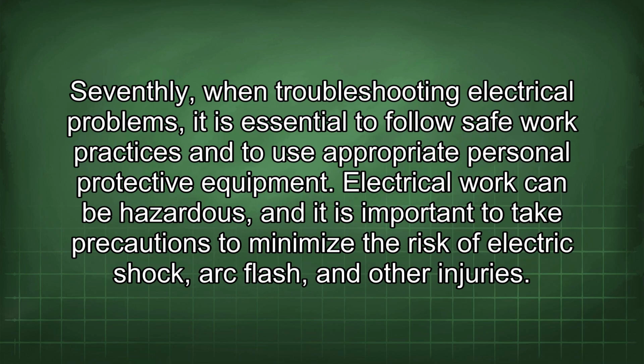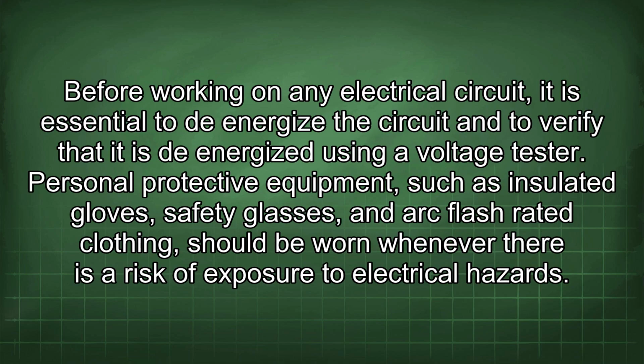Seventhly, when troubleshooting electrical problems, it is essential to follow safe work practices and to use appropriate personal protective equipment. Electrical work can be hazardous, and it is important to take precautions to minimize the risk of electric shock, arc flash, and other injuries. Before working on any electrical circuit, it is essential to de-energize the circuit and to verify that it is de-energized using a voltage tester. Personal protective equipment, such as insulated gloves, safety glasses, and arc flash-rated clothing, should be worn whenever there is a risk of exposure to electrical hazards.